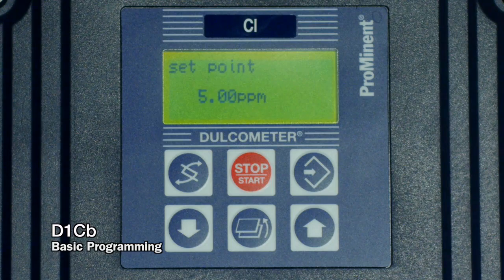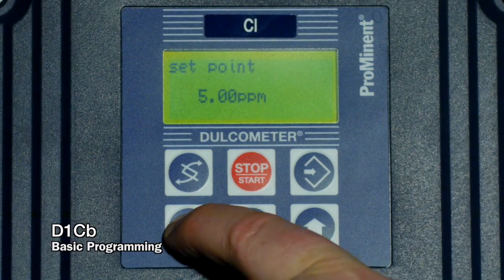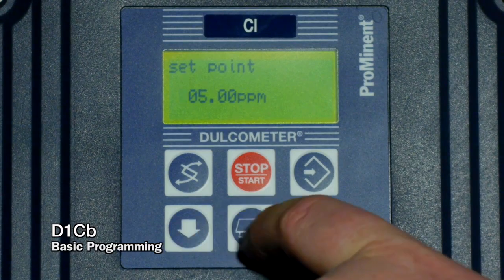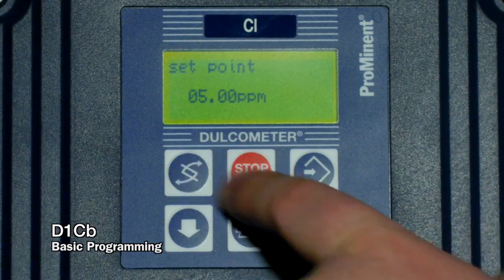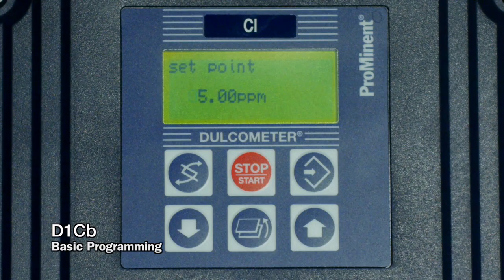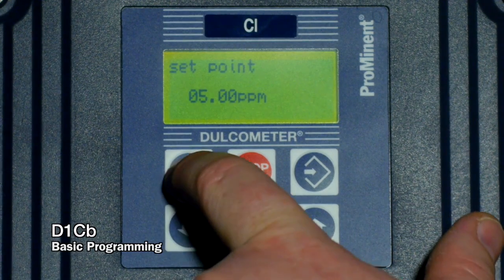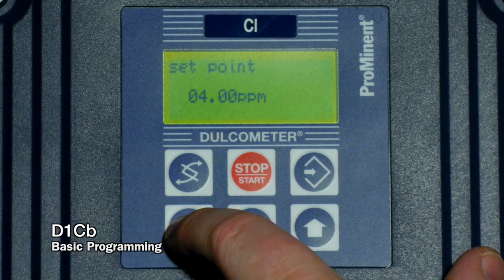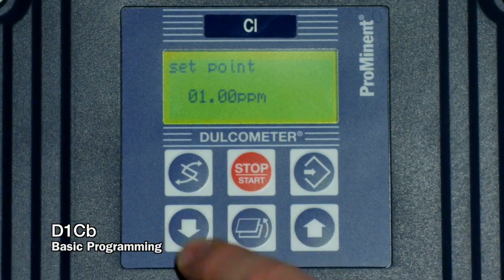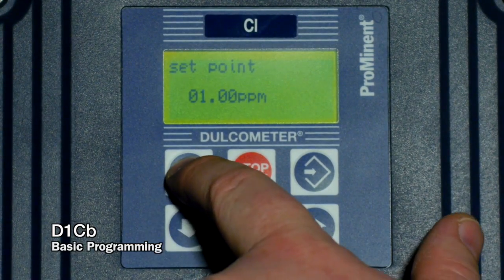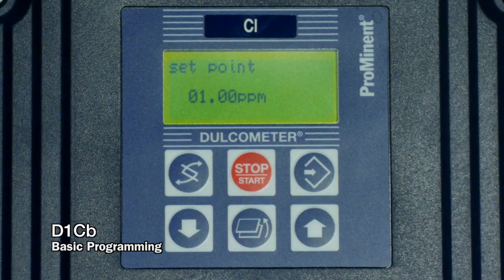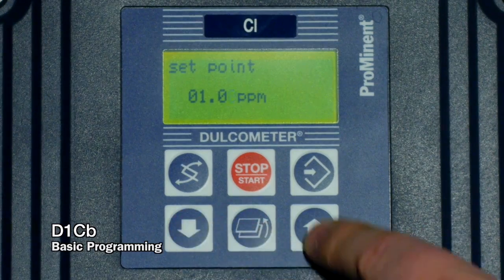5 parts per million could be rather high for a lot of processes, so be very aware that that also goes back to our default setting. Once we hit the enter button or the up or down arrow button, the first digit starts to flash, so we can set our set point. We want to change that to maybe 1 part per million. So whatever digit's flashing, we need to hover on. So we hit the change key until we're hovering on that digit. Then we hit the up or down arrow button for whatever's flashing, and we can change that.